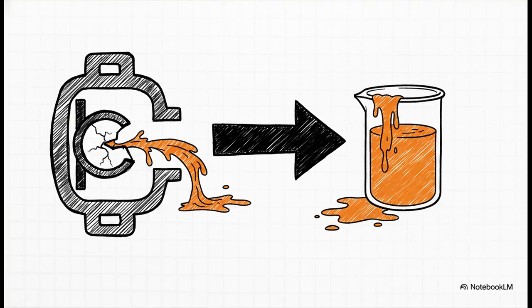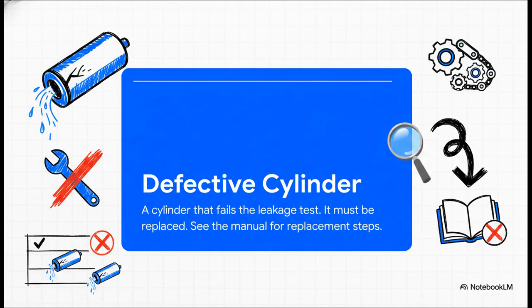It's really this simple and this direct. If you collected more than 1 pint of oil in that 30-second window, the service manual confirms it. The cylinder has excessive internal leakage. It means the seals inside have failed. And there you have it, the final verdict. A cylinder that fails this test is officially defective. There's no repairing it. The only solution is to replace it. And from here, the manual points you to the full replacement procedure, which is the next chapter in your repair journey.